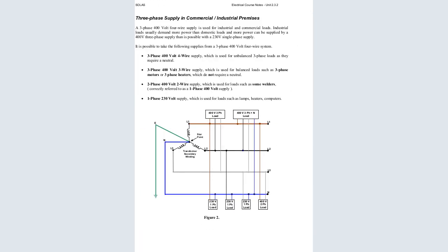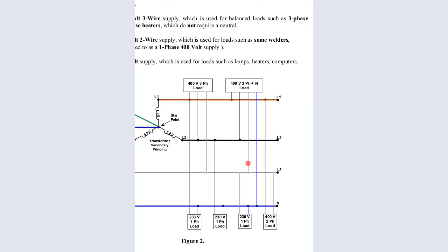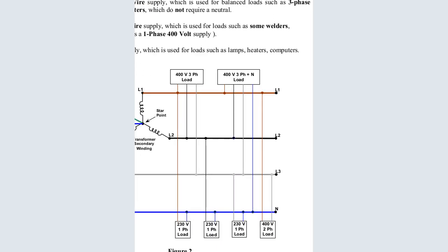Now we can get a 2-phase load. It is tapping 2 phases without a neutral. It is not a single phase. It is called a 2-phase. And that is why in the market we have a 2-phase transformer that can tap only two phases from the supply system. This is the load that is tapping the 2 phases. When it is tapping the 2 phases, meaning it is tapping 2 lives, live 1, and it can either take line 2 or line 3, but this one took line 3. So it can balance. It is called a 2-phase because it is tapping 2 live phases. This is a live phase and this is a live phase.